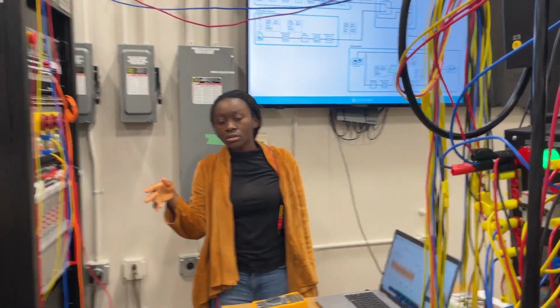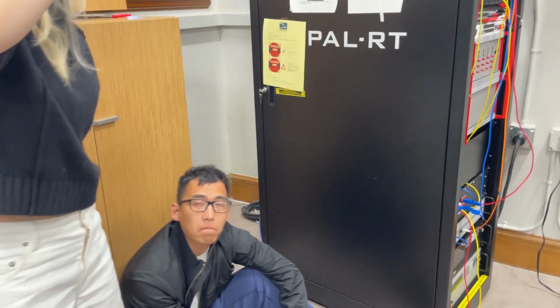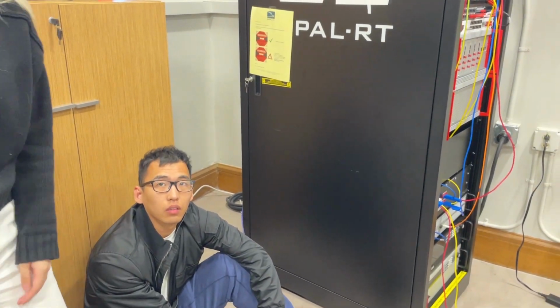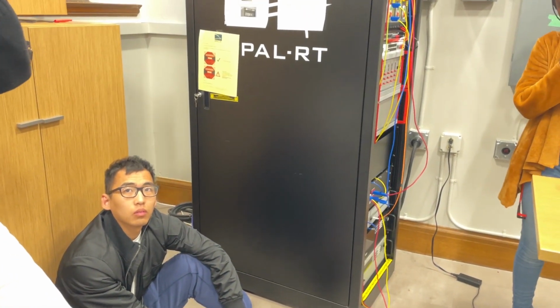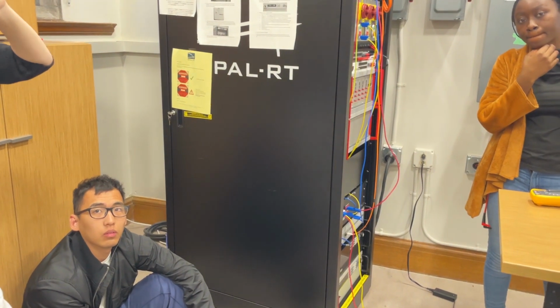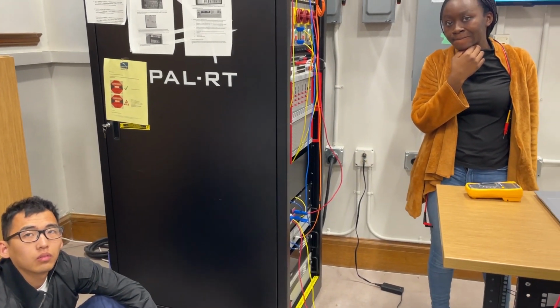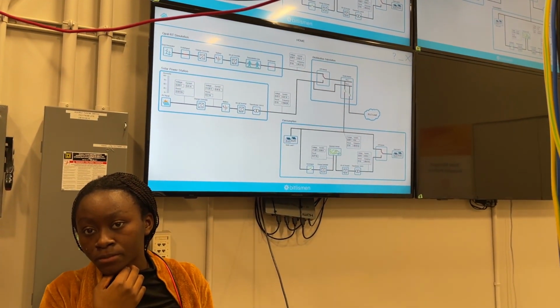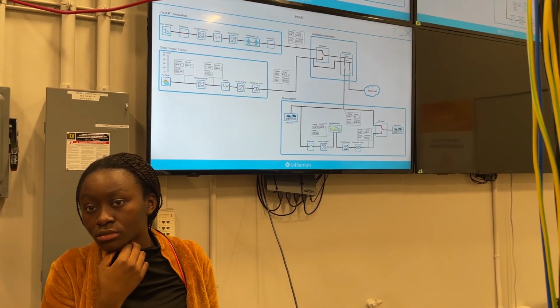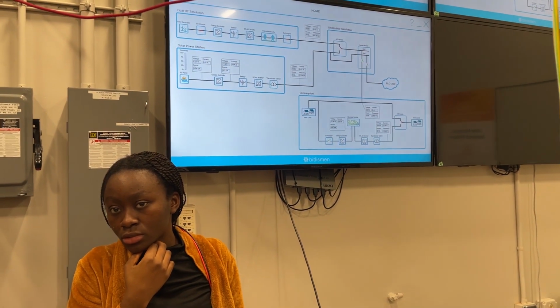You can connect two different sources to two different loads, but in case you would like to connect two different sources together, then you need to synchronize those, right? Yeah. So for this specific setup, you don't have a synchronization module. Later on, we can discuss and we can supply to you that kind of module as well. For this specific single line diagram, any given load is supplied with either one or the other source.